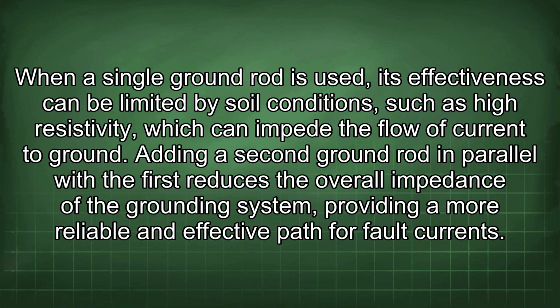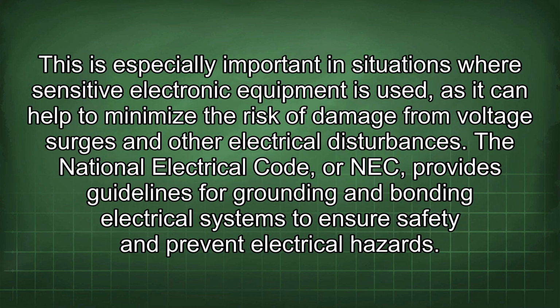When a single ground rod is used, its effectiveness can be limited by soil conditions such as high resistivity, which can impede the flow of current to ground. Adding a second ground rod in parallel with the first reduces the overall impedance of the grounding system, providing a more reliable and effective path for fault currents. This is especially important in situations where sensitive electronic equipment is used, as it can help to minimize the risk of damage from voltage surges and other electrical disturbances.